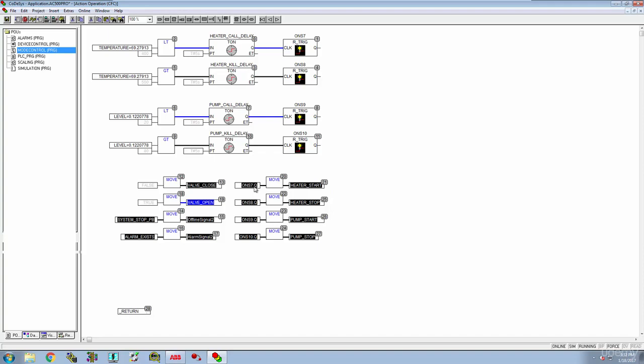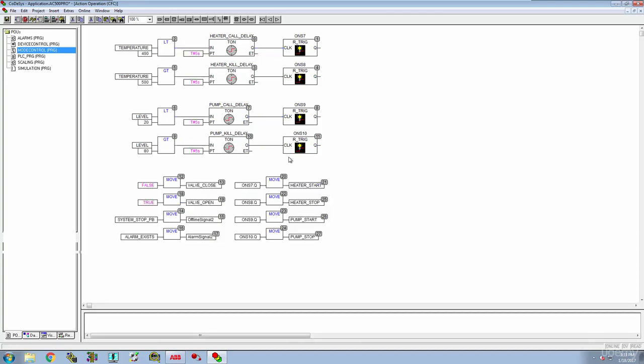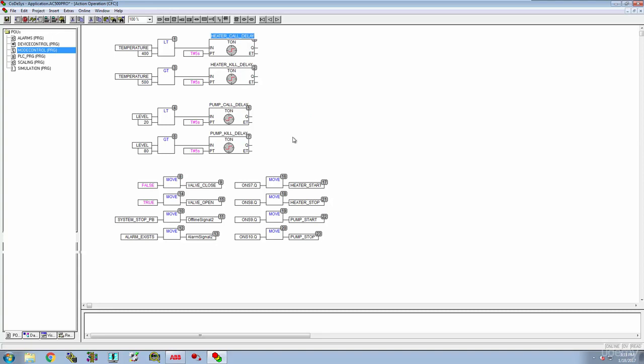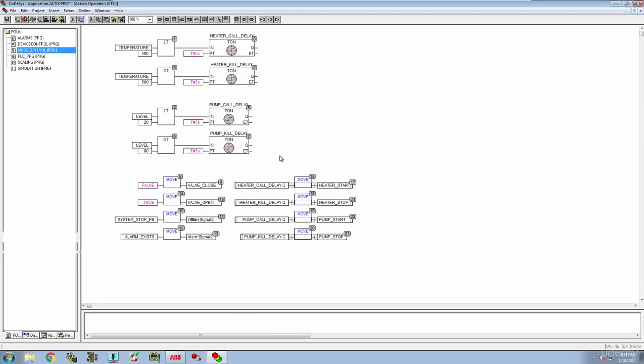Heater start should be energized, and right here we're moving that one-shot over to heater start — but that was just a one-shot. I'm guessing that instead of using a one-shot, let's try taking those one-shots out and running this right off of the timer. Let's stop, reset, come up here, get rid of all of these one-shots, and then go right off of these Qs. I'll paste that in, copy, paste — and I'm going to move these things a little bit for housekeeping. Let's select all of that and pull it over.